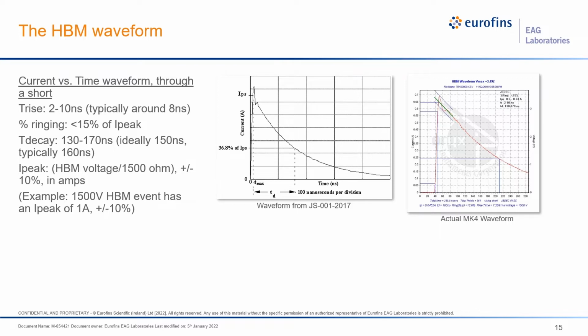The rise time for the waveform is allowed to be between 2 and 10 nanoseconds. Typically, it's around 8. Percent ringing has to be less than 15% of the peak, and on most testers being built today, that's not an issue. A perfect decay time would be 150 nanoseconds, but typically, again, it runs around 160 nanoseconds, which is well within the spec of 130 to 170 nanoseconds.